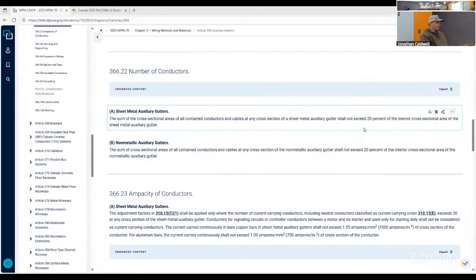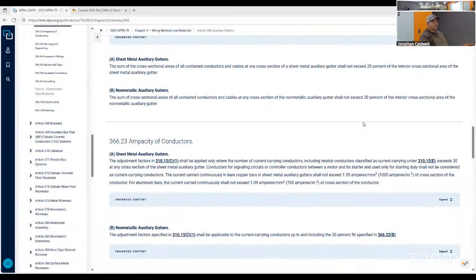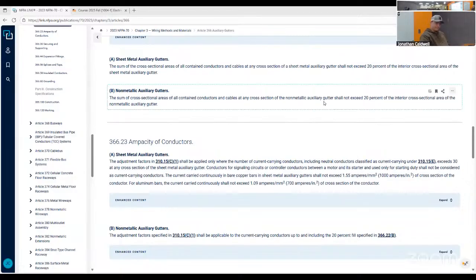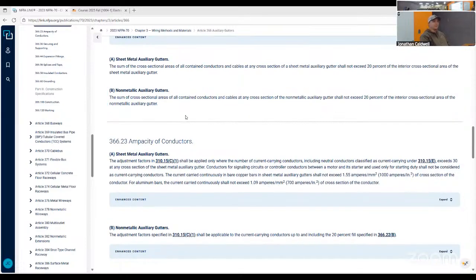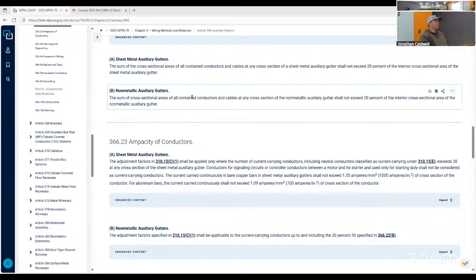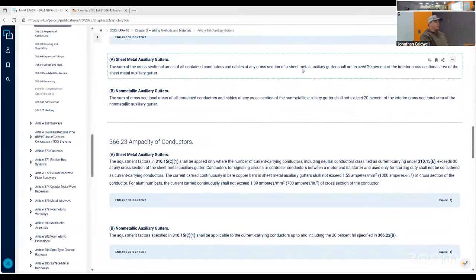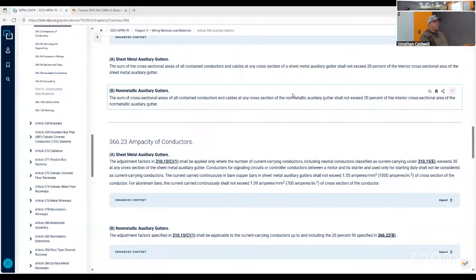And also can't exceed 20%. So if you do keep them grouped together, it's going to be nice and tidy. And I'll be honest with a lot of you, I've seen a lot of gutters that look full to the brim and they still don't meet the 20% rating. We've done the math, we even had the inspector do the math, and it still didn't exceed, even though you couldn't get another set of number 12s into it. It's extremely difficult to meet this, so at that point, you would need to do temperature derating and go from there.